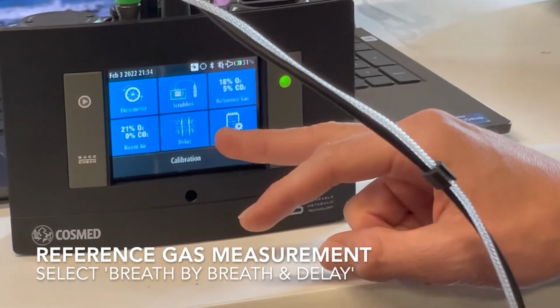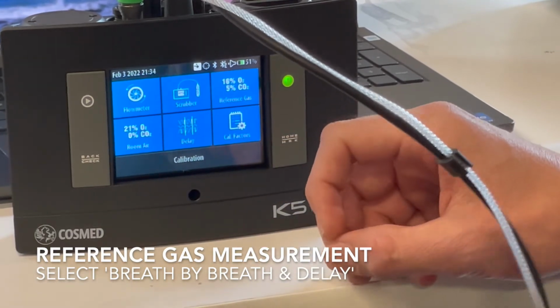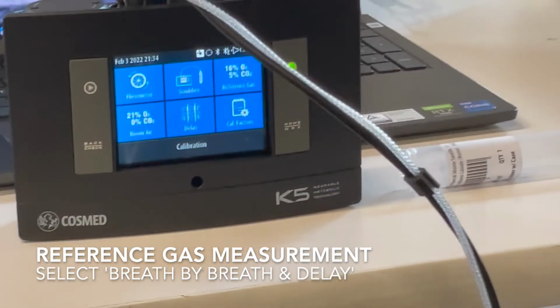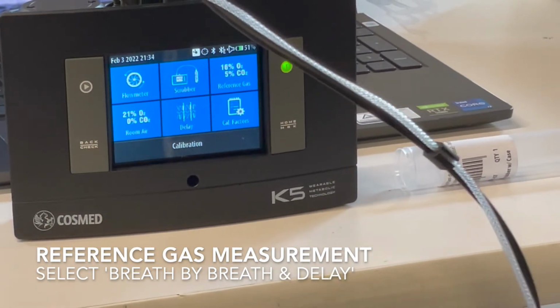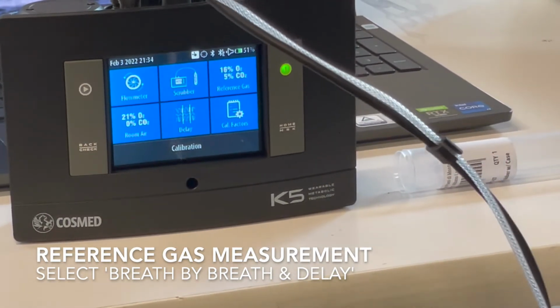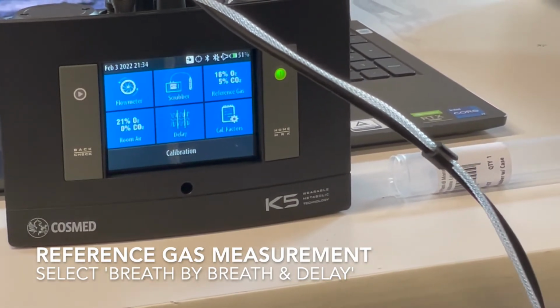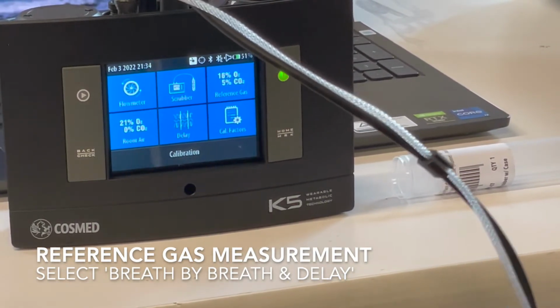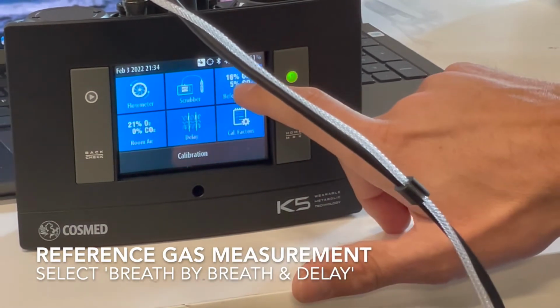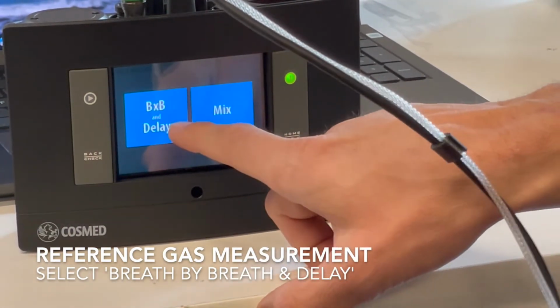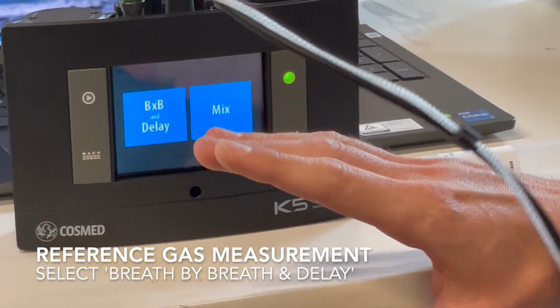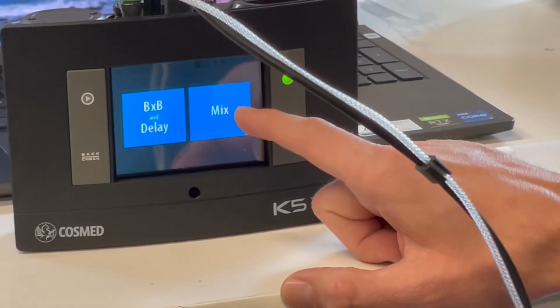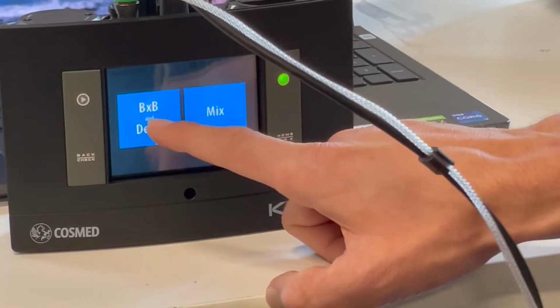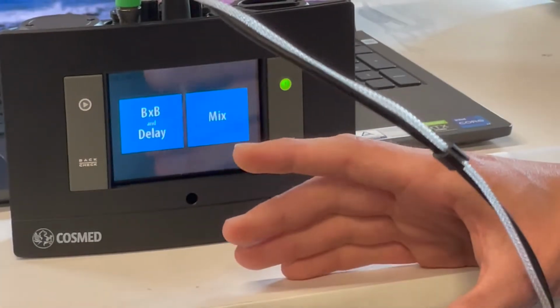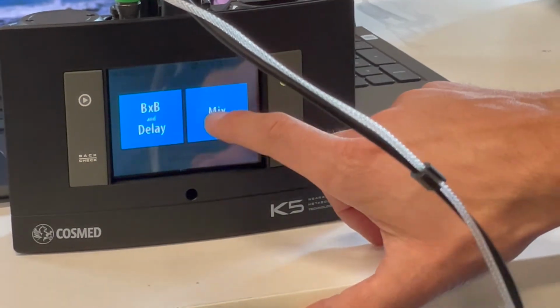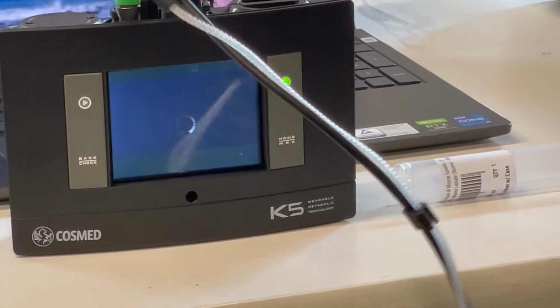And basically what the delay test looks like is it just wants to establish a baseline of inspiration and expiration. So it just wants to make sure that it can average tidal volume and get an accurate measurement. So I'll show you what that looks like. But again, if you do breath by breath, you don't have to do anything with that. We're just gonna do a mixing chamber because it's pretty much the same. We're just gonna have to do the delay manually so I can show you what that looks like. So we'll go mixing chamber.